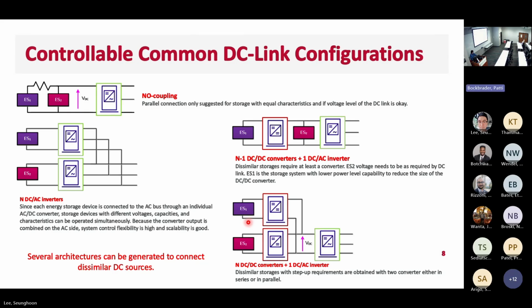The final configuration uses N DC to DC converters and one DC to AC inverter. This gives improved controllability. Each storage unit is processed through its own DC to DC converter, making it suitable for systems with highly dissimilar storage technologies. Although it provides the highest level of flexibility, it increases losses and overall system cost. Ultimately, selecting the right DC-link architecture involves balancing flexibility, efficiency, cost, and system complexity based on the application's specific requirements.